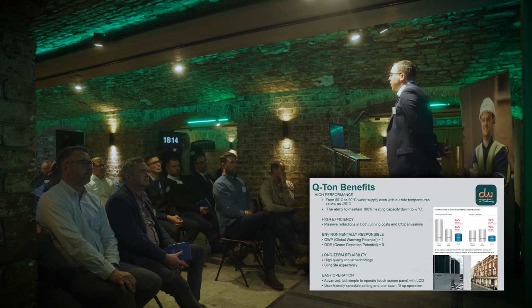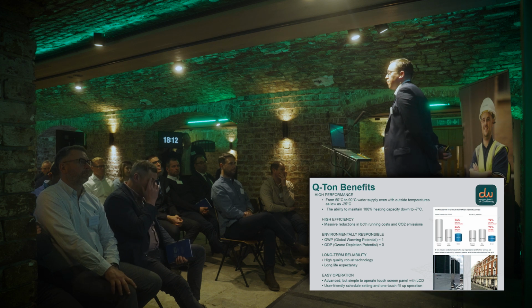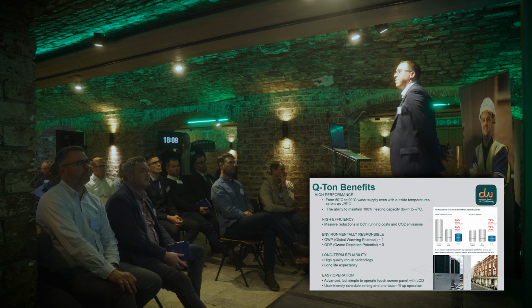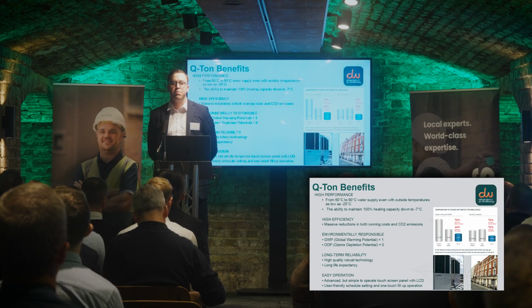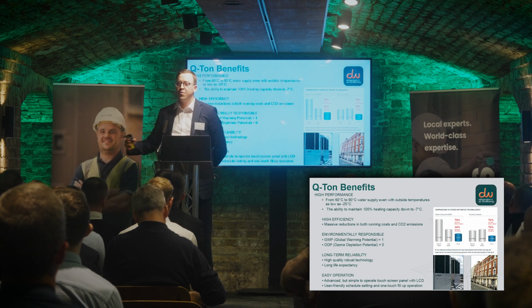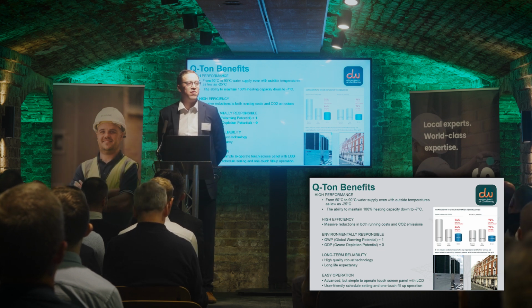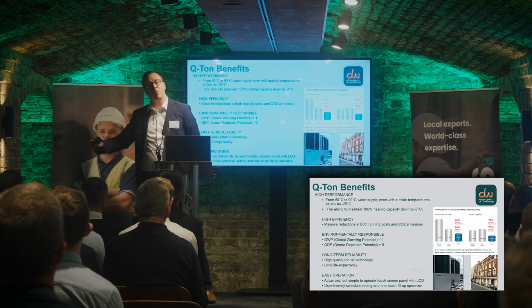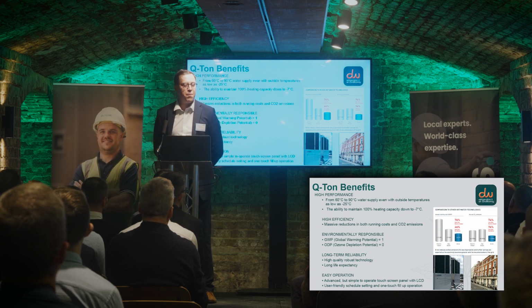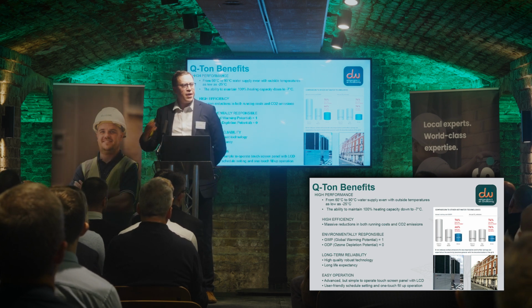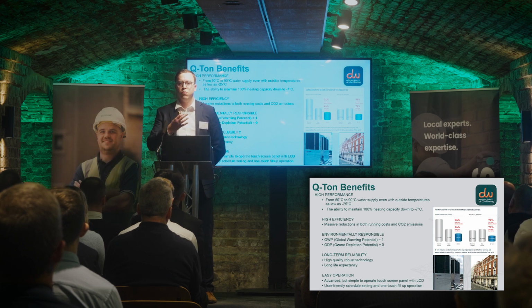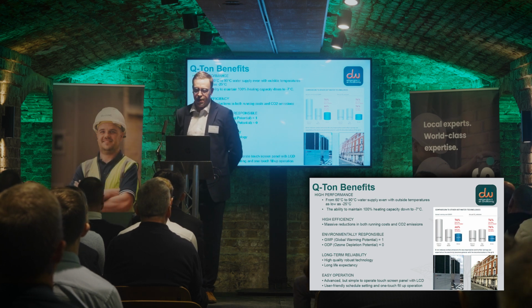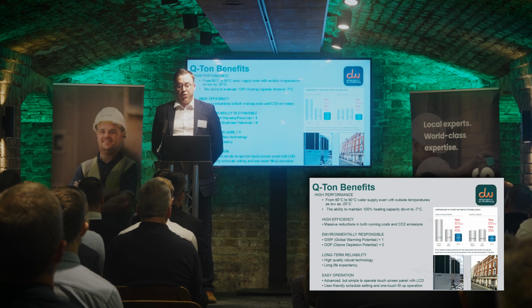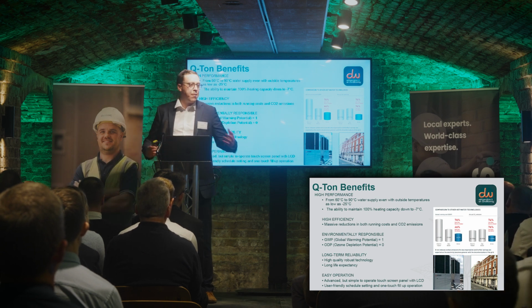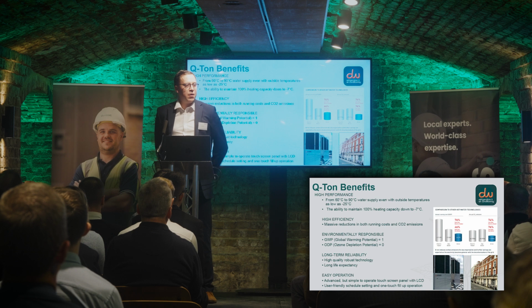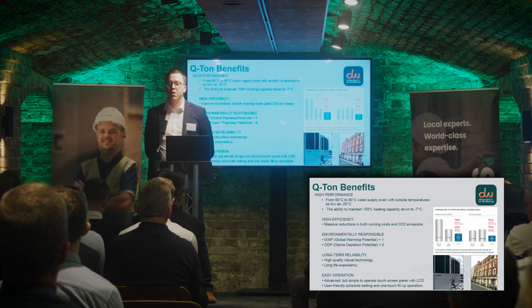What are the benefits? Well, we can deliver hot water temperatures from 60 to 90 degrees, even down to outside temperatures as low as minus 25. You'll get 100% capacity out of the unit down to minus 7, and then you'll see a small drop off the lower we go in terms of temperature. In comparison to a gas or electric boiler or heater, we see reductions in running costs of anywhere between 76 and 46, depending on the heat generation, and an efficiency saving of 75%.